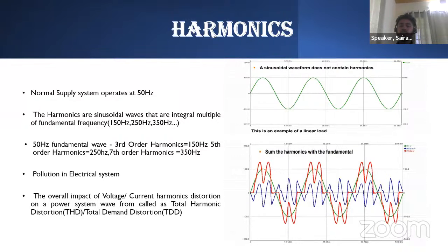The overall impact of voltage and current harmonic distortion will be called total harmonic distortion or total demand distortion. It depends upon the loading condition at the point of time when we are measuring this. There will be a standard for 100% loading, but while we are doing the assessment, industries won't be at 100% loading of the site. So at 50% or 60% loading, we will be doing this analysis and we will mention it as total harmonic distortion. If we do the same thing at the time of 100% loading, then it will be considered as total demand distortion.